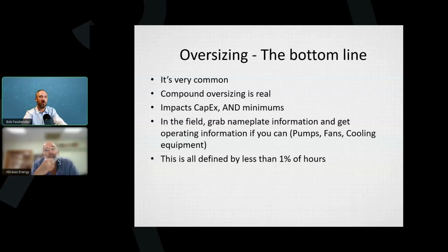Yeah. So the problem with the oversizing, if you're going to slap a variable speed drive onto the motor to convert it to VAV, is how slow can it go, and what airflow can we drop it down to? That's right. That's a huge assumption. Absolutely. That's right.